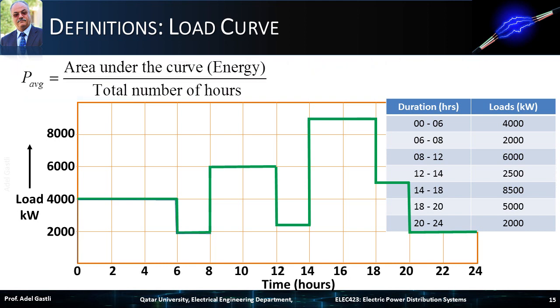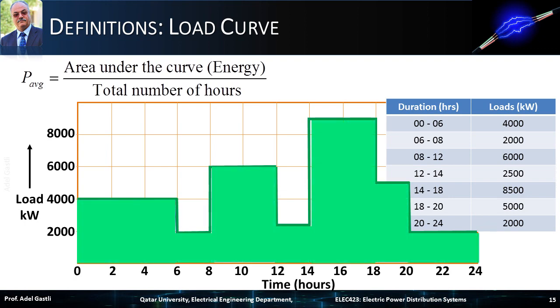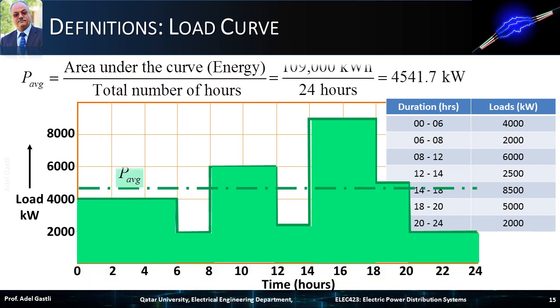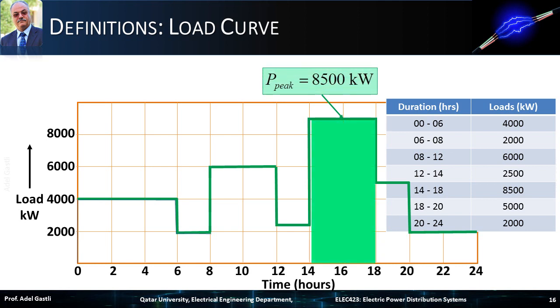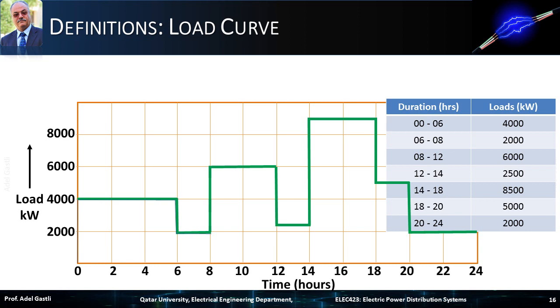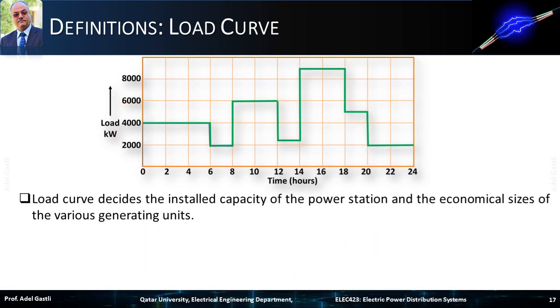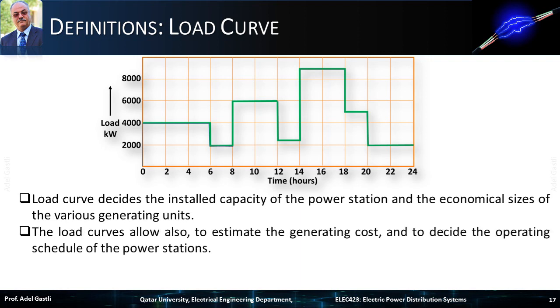The average load in a particular day equals the total energy, or area under the curve, divided by the total number of hours. In this case, it is 109,000 kWh divided by 24 hours, which equals 4,541.7 kilowatts. The peak load during the day is 8,500 kilowatts, occurring between 2 and 6 p.m., which also represents the maximum demand on the power station. The load curve decides the installed capacity of the power station and the economical sizes of the various generating units. It also allows estimation of generating cost and scheduling of power station operations.